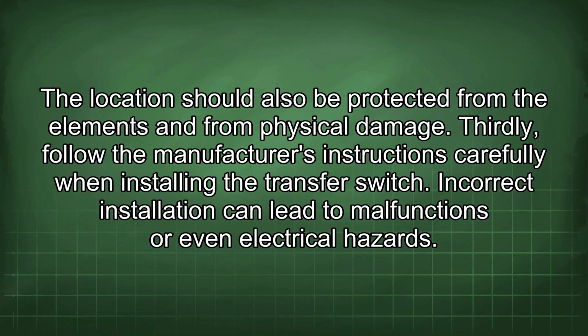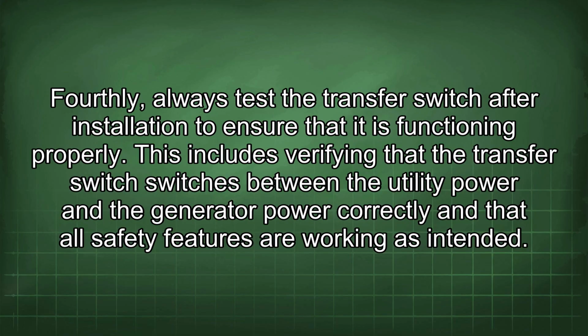Thirdly, follow the manufacturer's instructions carefully when installing the transfer switch. Incorrect installation can lead to malfunctions or even electrical hazards. Fourthly, always test the transfer switch after installation to ensure that it is functioning properly. This includes verifying that the transfer switch switches between the utility power and the generator power correctly and that all safety features are working as intended.